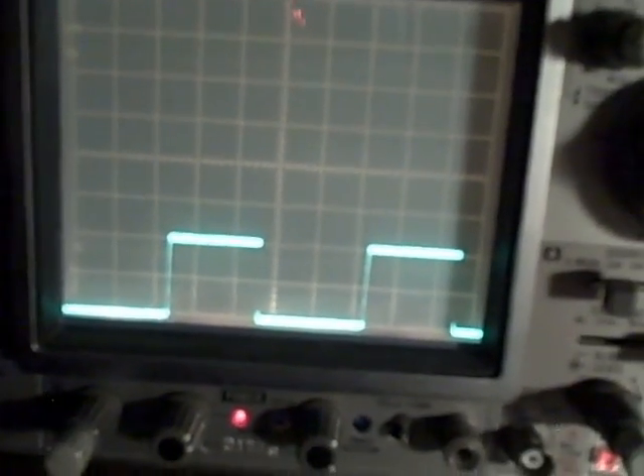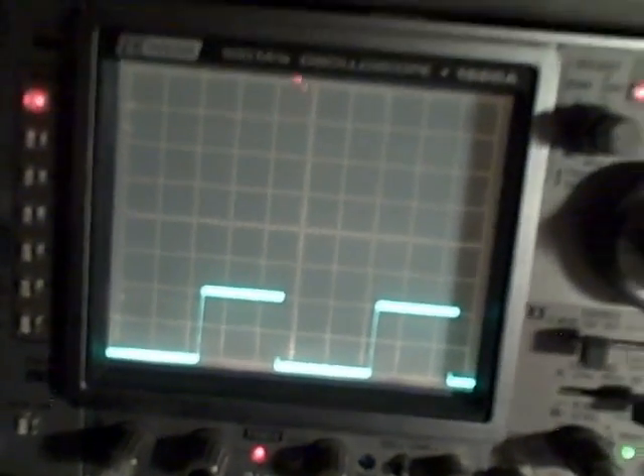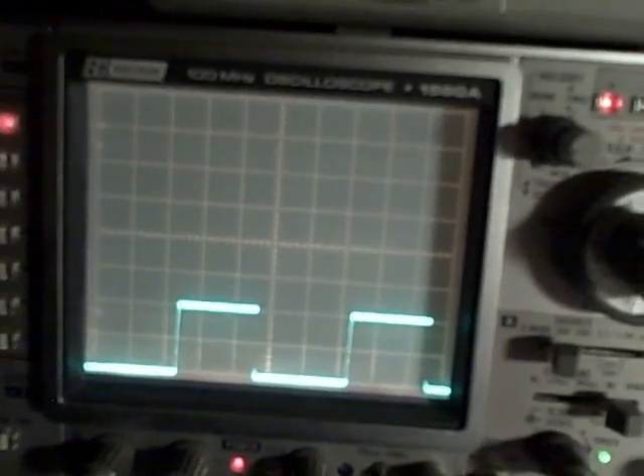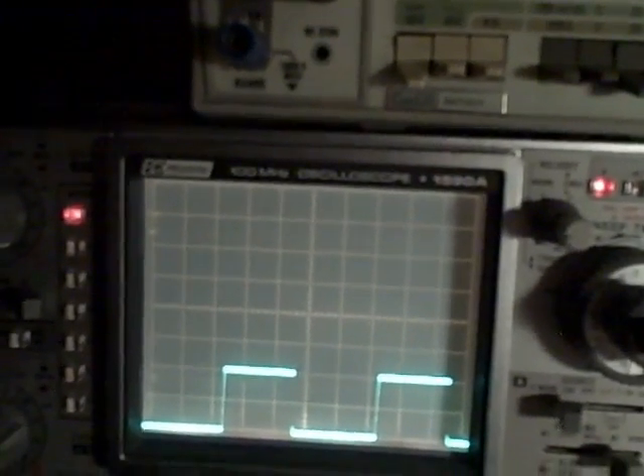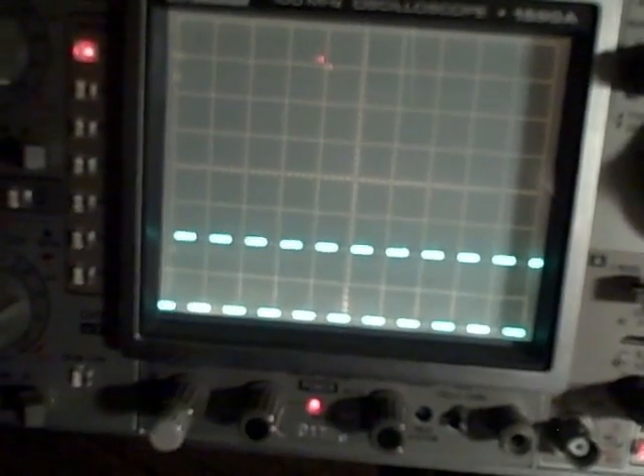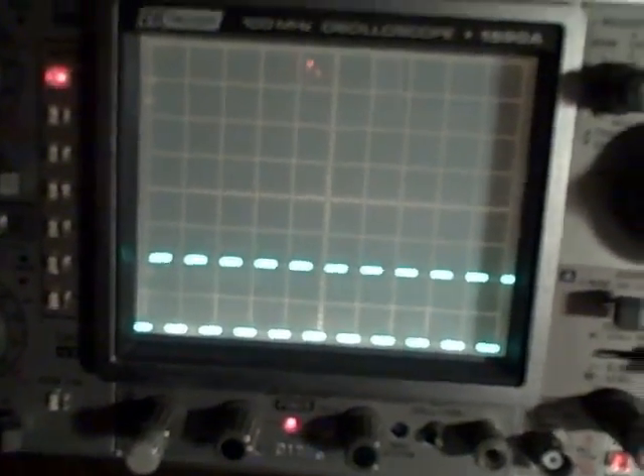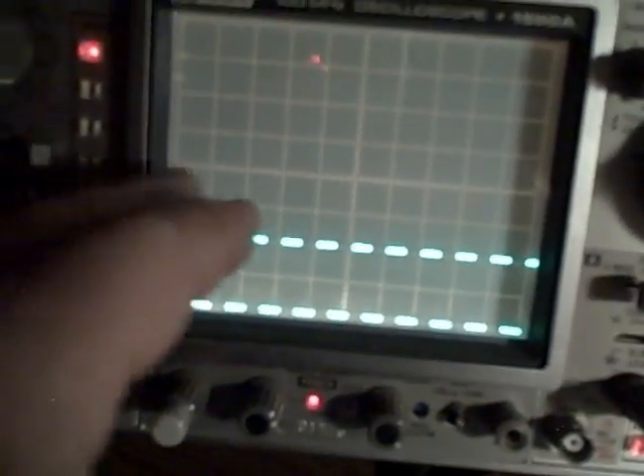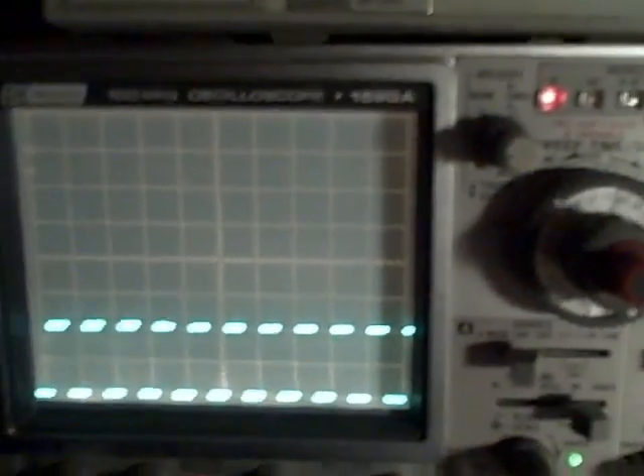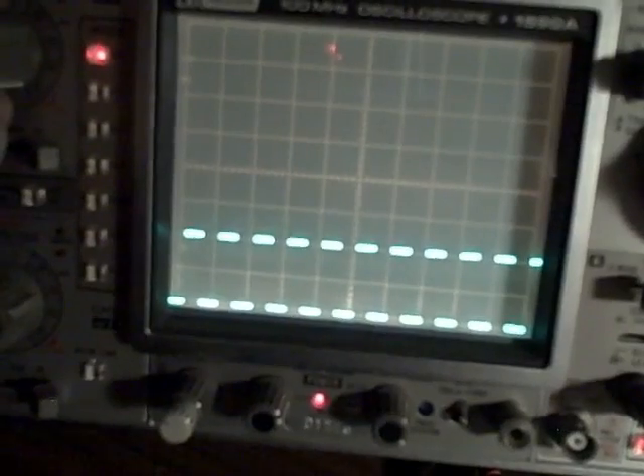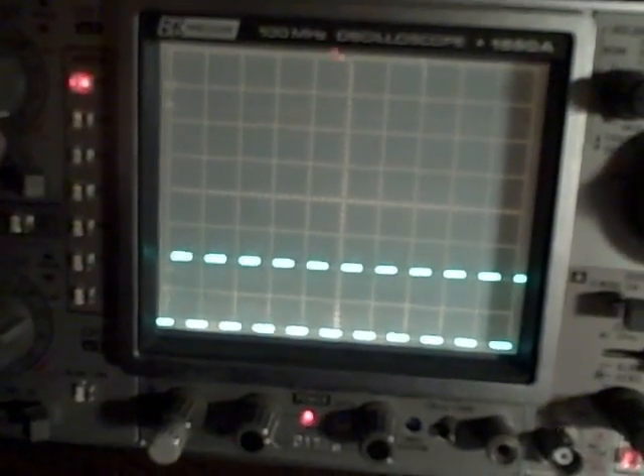Let's turn up our frequency a little bit. There we go. So right now I'm on 5 millivolts per division. I've got 2 divisions, and I've got a square wave coming in at 0.1 milliseconds. Yeah, let's go to 1 millisecond. Alright, there we're 1 millisecond per division on the scope, and I've got 1 millisecond pulses coming in, so I'm going to see a pulse every division, and I do. And I'm coming in at 10 millivolts. On a 5 millivolt vertical range, I've got 2 divisions, and that's 10 millivolts. So I've got a 10 millivolt pulse at 1,000 hertz coming in.